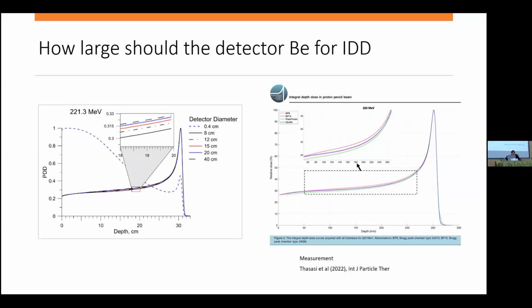So here's a publication. I'll show some more data from mine, but just to see that if you have detectors of different sizes, so this 0.4 cm detector, this is actually what we would call a percent depth dose. As your proton beam is going in, if you look at the central axis, so look at something that has maybe a 4 millimeter diameter just going all the way down, the beam you'd measure would look like this. So high here with a Bragg peak there. The bigger you get your detector, the more you're going to be measuring, and you're going to see that you're going to measure more like this. And with these different sizes, you're going to get a difference here.